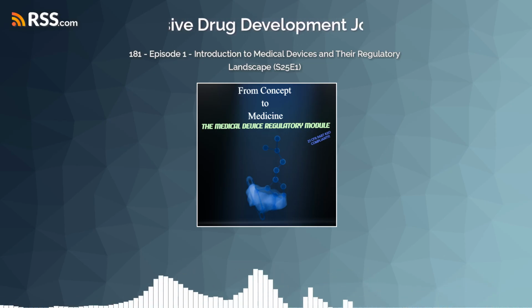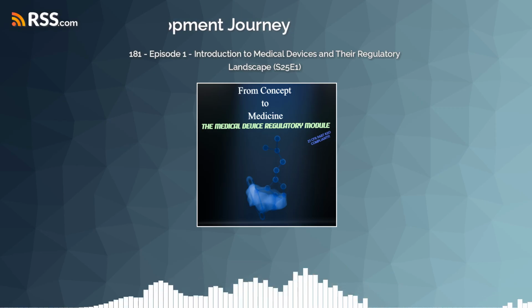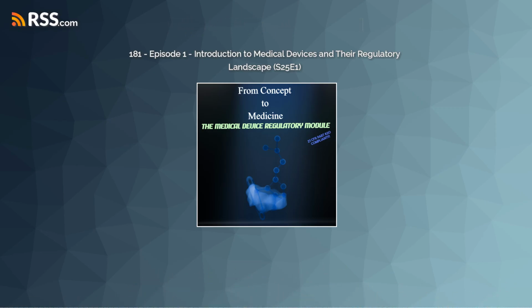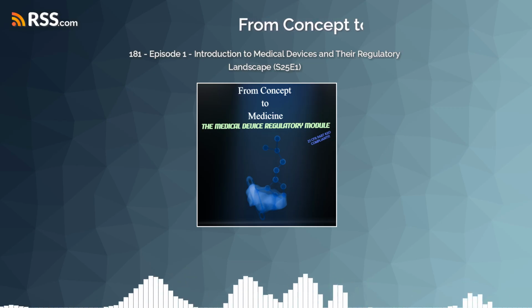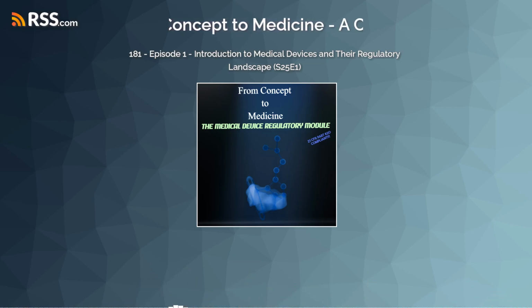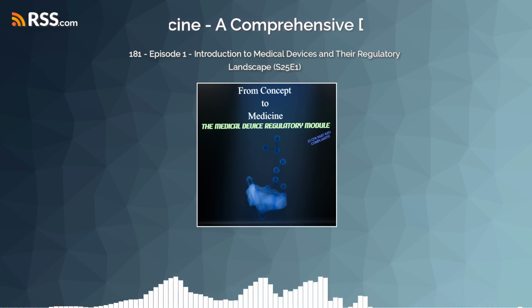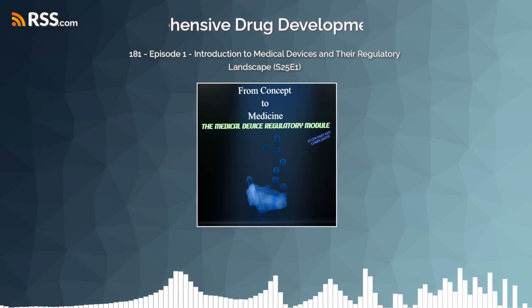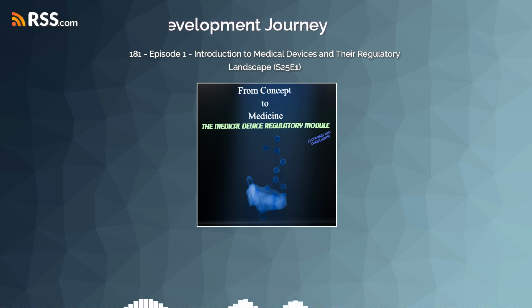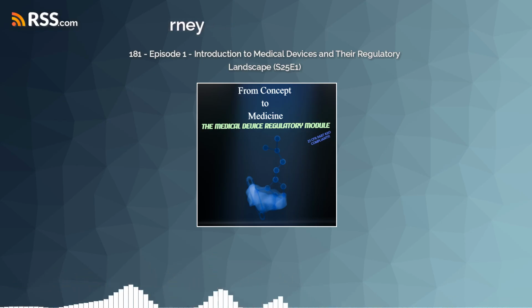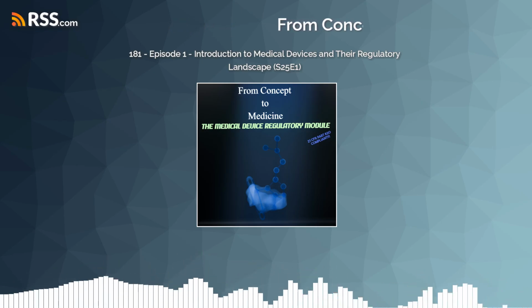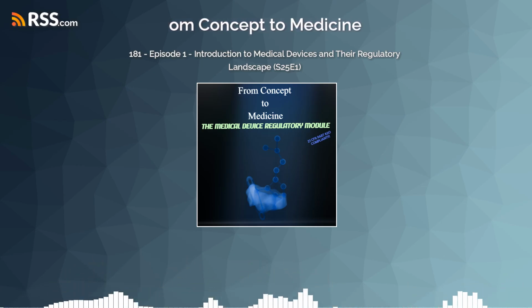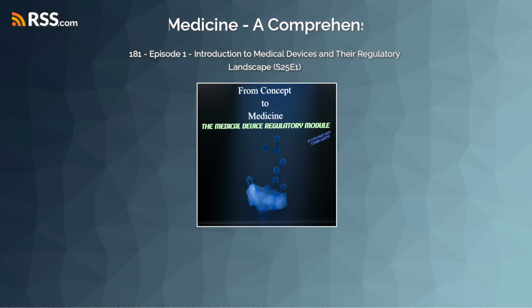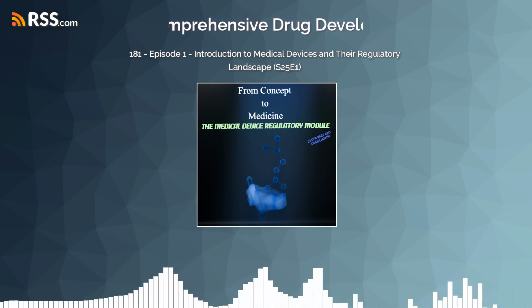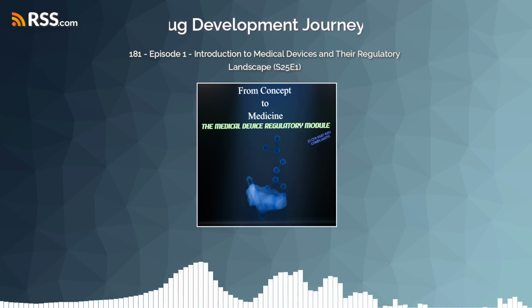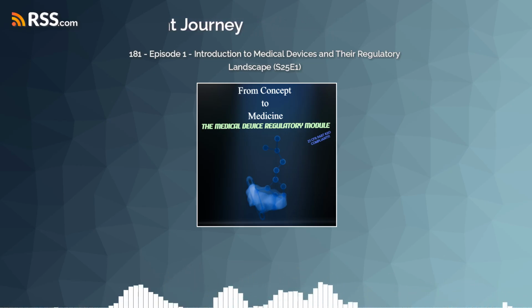Now, contrast that with the FDA's pre-market review. A 510(k) is focused on that substantial equivalence comparison. A PMA is a deep scientific dive into the device's specific data by FDA's own experts. While a QMS inspection happens eventually, and often pre-PMA approval, it isn't always the primary focus of the initial 510(k) clearance decision itself. So different focus points in the review. EU, maybe more QMS-centric upfront for CE marking. FDA, more data equivalence-centric for clearance approval. That's a reasonable simplification, yes. Both demand strong data and quality systems, but the review structure and emphasis can feel quite different. Manufacturers really need to understand both systems thoroughly if they plan to operate globally.